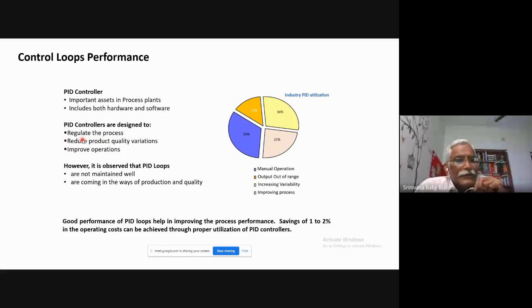By doing so, it will reduce the quality variations in the process variable and also improve the operation, because the whole control logic works along with all other automation logic, so that the whole plant is operated in an automatic way, improving the operations. Okay, so PID control plays a very important role in the operation of the plant. But what has been observed is they are not maintained well, and sometimes because of the poor performance of PID controllers, it even affects the production and the quality of the product that is produced.